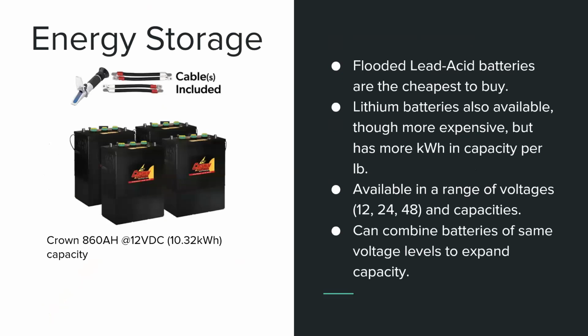Now, all that generation is great, but it's worthless unless you can store it. There are many different types of storage out there, including lead acid, flooded lead acid, sealed lead acid, and then you've got your lithium ion. However, lithium ion is more expensive, but it has more kilowatt hours capacity per pound. For this project, we went with this 860 amp hour at 12 volt DC, which equates to 10.32 kilowatt hours capacity. It comes with all the cables and batteries.